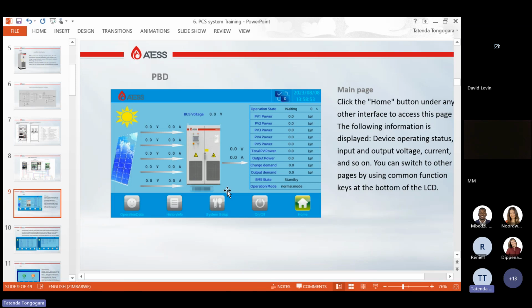So the first page, the front page of your PBD, what you see is your PV voltage, your current, and then PV1. So the input 1 connected to the first MPPT, it will show you the kilowatts that it is producing here. And then the output, the total PV power, this is the summation of these 5. And then charge demand. So your PCS is connected to the PBD, and it will send information to the PBD of the charge demand, the charge that's required to charge your batteries. This will be coming from a BMS. Your charge demand can be 50 kilowatt, 100 kilowatt, depending on what SOC your battery is at. And if the battery is full, the charge demand will be 0 here.